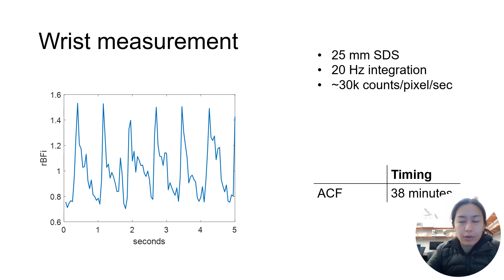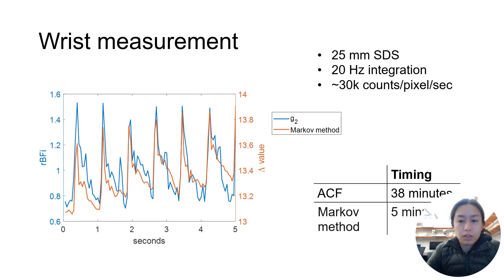Here we have a wrist measurement at 25mm source detector separation, 20Hz integration, and around 30,000 counts per pixel per second. Acquired with the raw photon detection event mode, the pulsatile blood flow here is clearly visible.